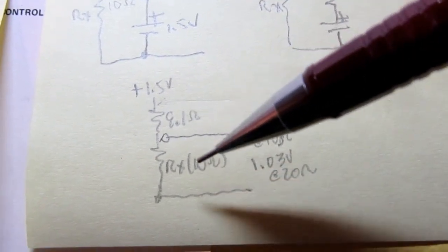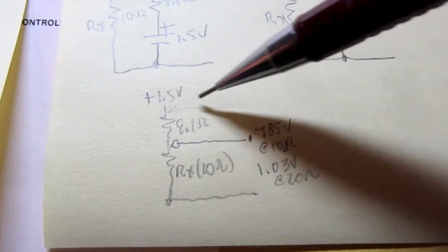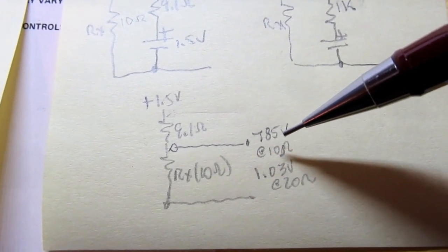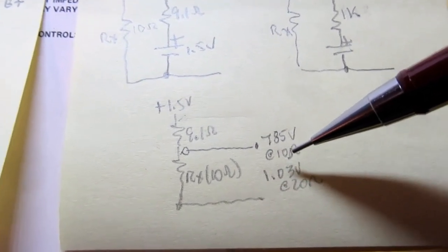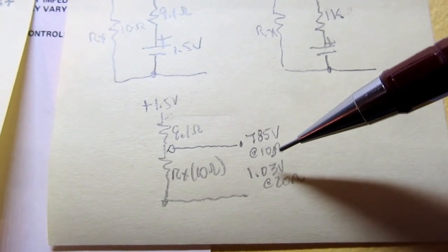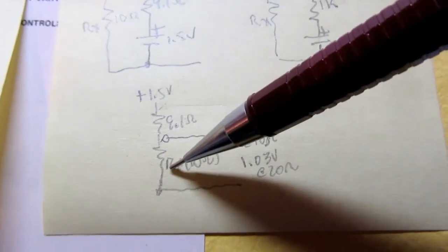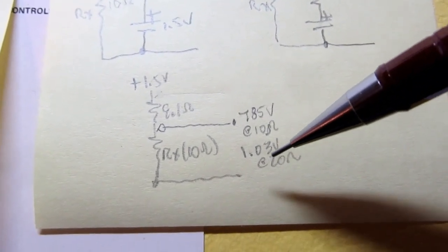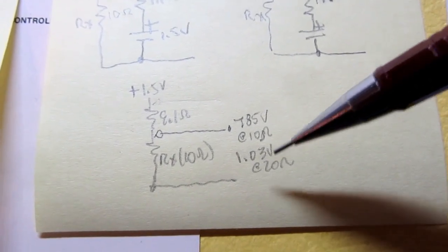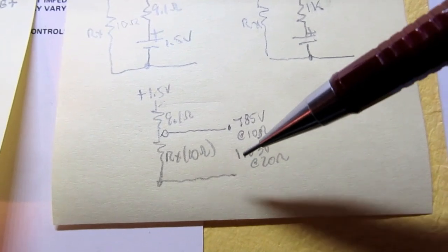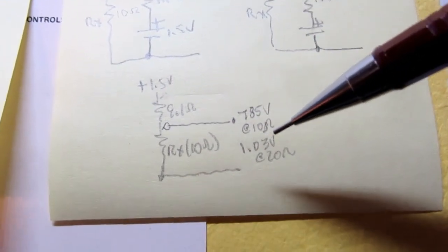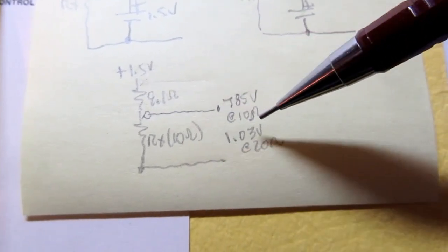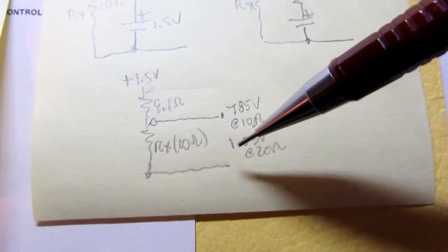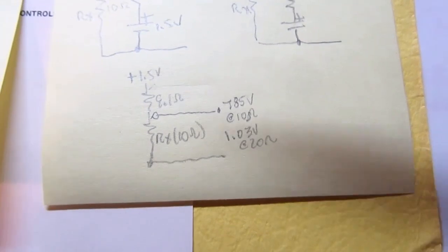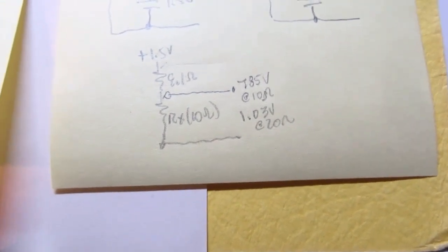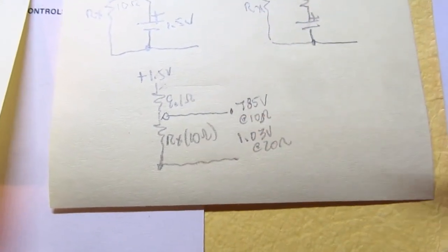So let's take, for example, let's say that we do have a 10 ohm resistor here. If we do the Ohm's law to this, you'll end up with 0.785 volts presented to the rest of the meter. And that's assuming that you've got a 10 ohm resistor under test. And let's see if we double that and made it a 20 ohm, you do the math, you end up with 1.03 volts. So it's a higher voltage being developed for a higher resistance, and so on. But you can see 20 ohms is double 10 ohms, but you don't get double of 0.785 volts. So already we've got a nonlinear response, which is why the scale on the meter in the ohms mode is very nonlinear. It has to take into account this kind of response.